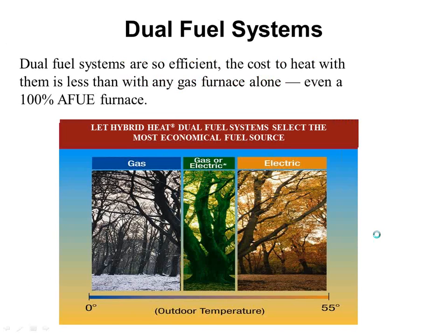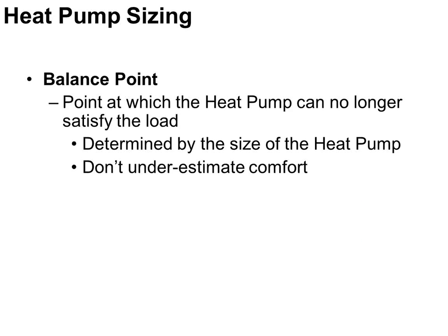Now in reality, what you could always do is you can keep putting in a bigger and bigger and bigger heat pump to get the heating BTUs that you want, right? If you have a cooling load of, let's say, 3 tons, and I have a heating load of 8 tons, I could put an 8-ton heat pump in and get all the heating BTUs that I could possibly want when it's minus 10 degrees outside, right? Just keep putting bigger and bigger surface areas in there, bigger and bigger coils, bigger compressors. The problem with that is once I go back to cooling mode, if I have an 8-ton condensing unit on a 3-ton peak load, there's no way I'm going to be able to maintain that thing and operate it and be able to get any decent dehumidification out of it.